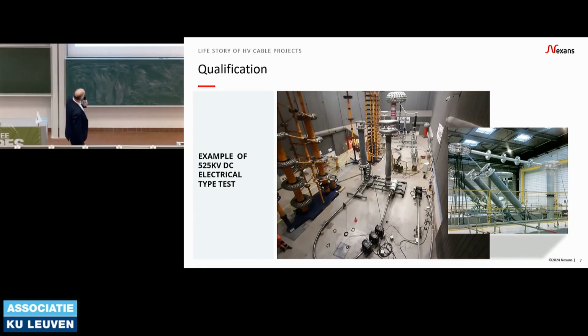You see here it's a DC cable with 500 kV sealing ends. These terminations are mostly used for laboratory purpose on the right-hand side, and then you have a dry termination, which is a GIS termination at the bottom here. You see here the size of termination, we are speaking about more than 6 meter high termination, so you need a lot of room to make your qualification. This kind of qualification can take up to 2 years, so very long time.